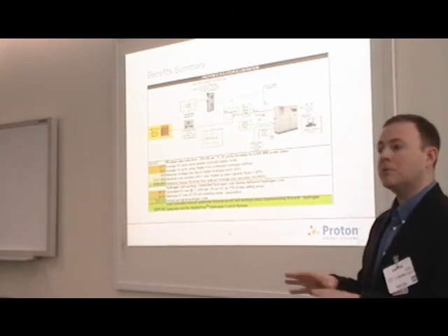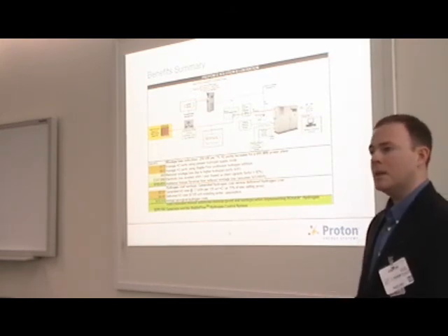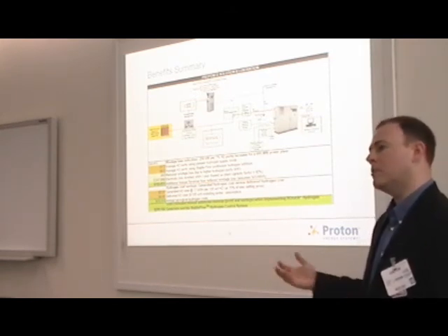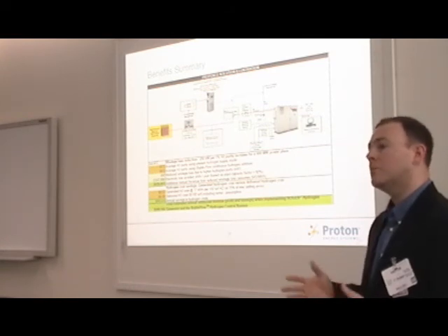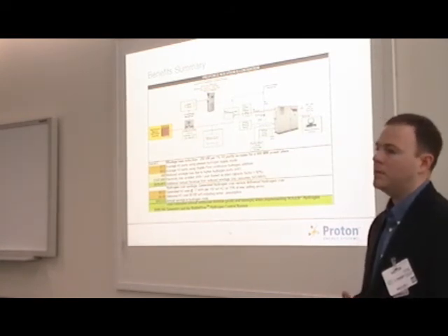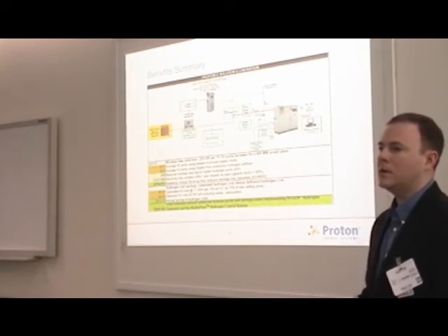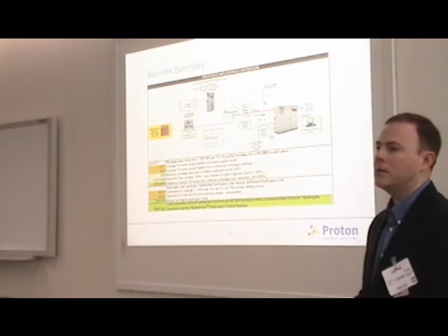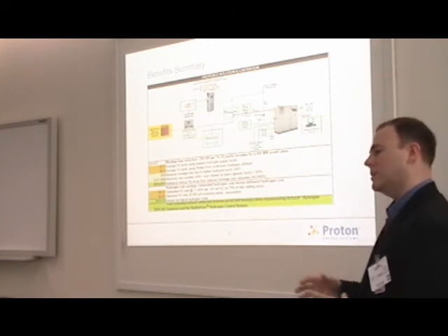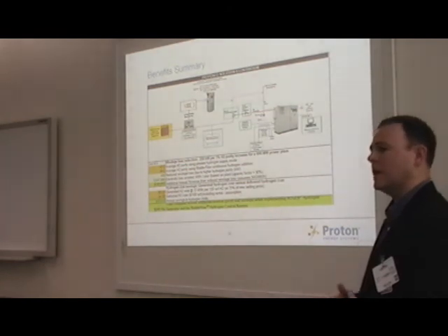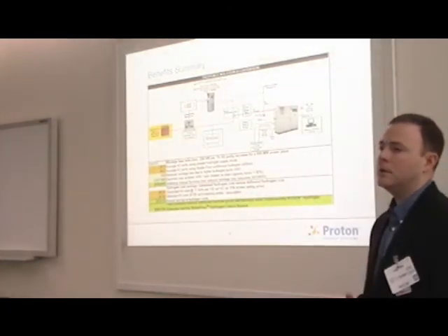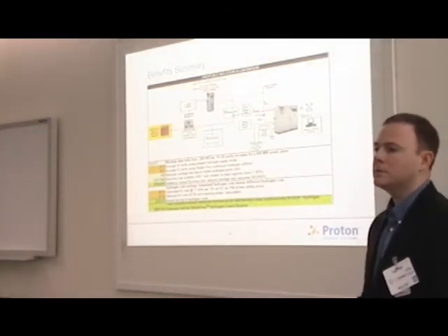Most people would put in the hydrogen generation for the daily makeup, and then they would have some alternate, maybe bring in a tube trailer for an outage, or a small tube trailer. Some of the small sites would go with maybe an 18-pack once a year during an outage. Other than that, they've been able to completely separate their ties from delivered hydrogen, other than maybe the once a year outage.